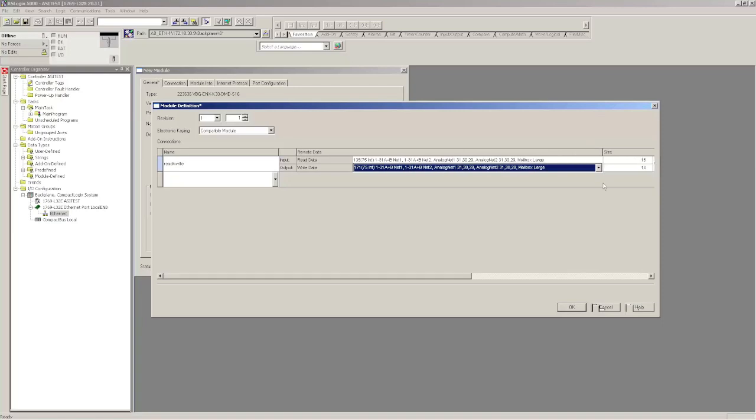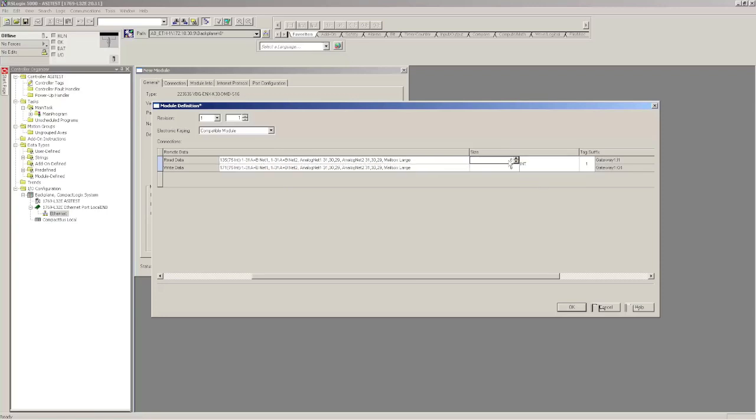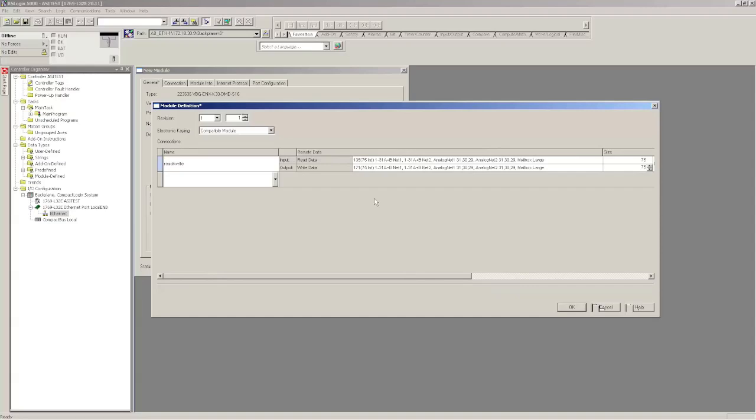You can see here that I'm mapping 1 through 31a and b on Network 1, 1 through 31a and b on Network 2, Analog, Nodes 29, 30, and 31 on Network 1 and 2, and then the mailbox at large. I'm doing that for both Inputs and Outputs. This string also shows the length: 75 Int. So I need to make sure that I change it to Integer and make the length 75. The other thing I want you to notice is these numbers in the beginning, 135, 171—keep that in your mind because we're going to use it later in this example to pull the CSV files.